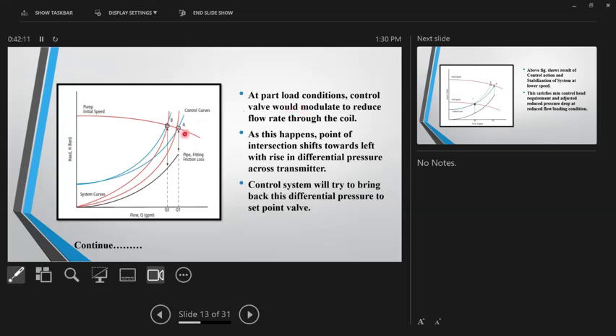So again, to our curve, this was the initial curve. This was the fixed head. Now the flow has reduced. It has, let's say, gone to B to match our new Q2 requirement. A problem again, what has happened is the control head distance has increased. So if you expect the pump to go straight away to the left and settle out there, it won't happen. As this happens, the point of intersection shifts toward the left with a rise in differential pressure across the transmitter. This would happen when you start to close the valves.